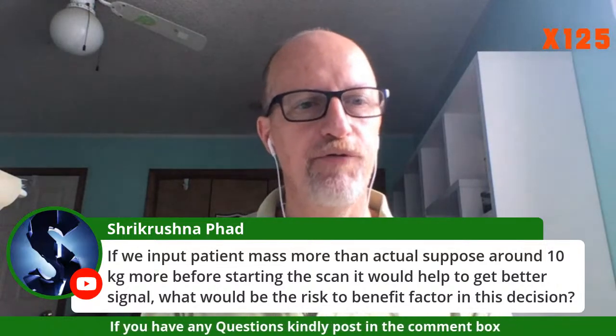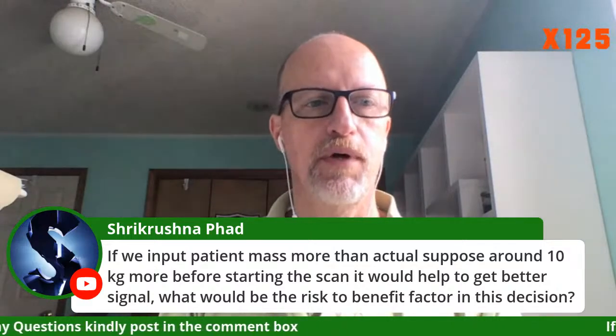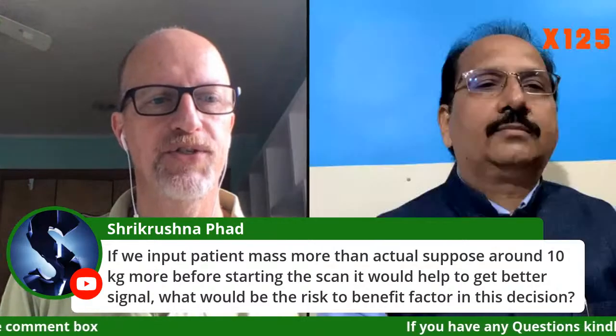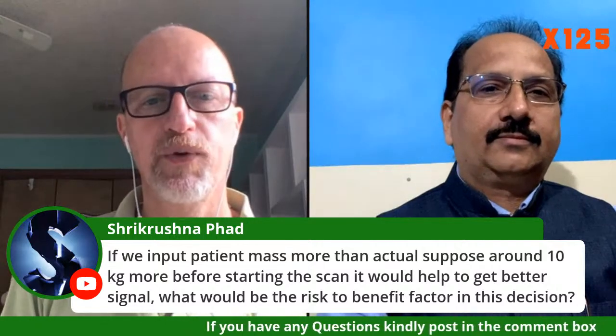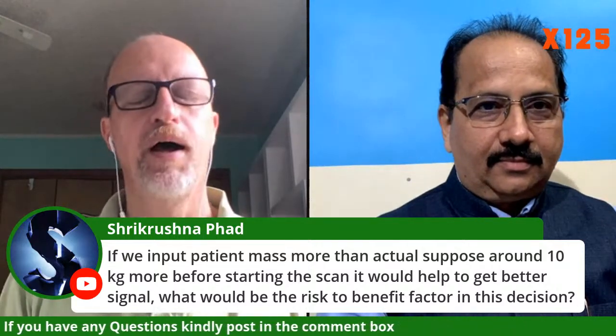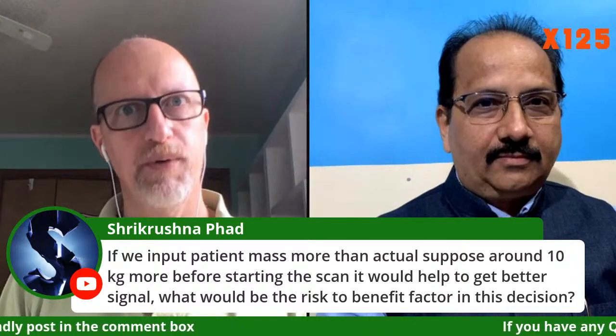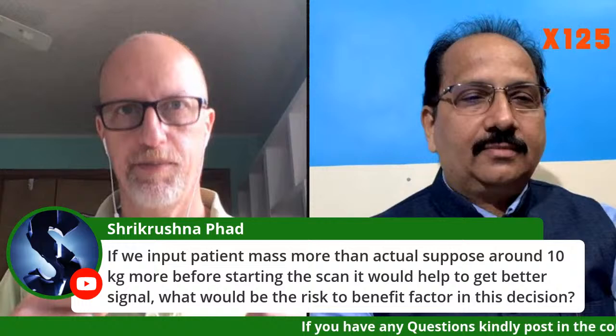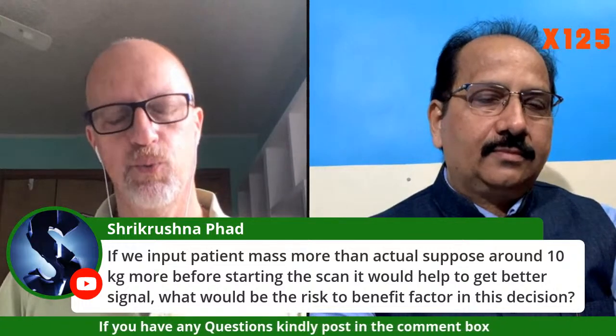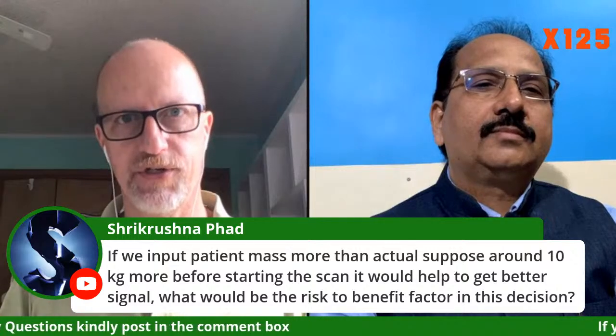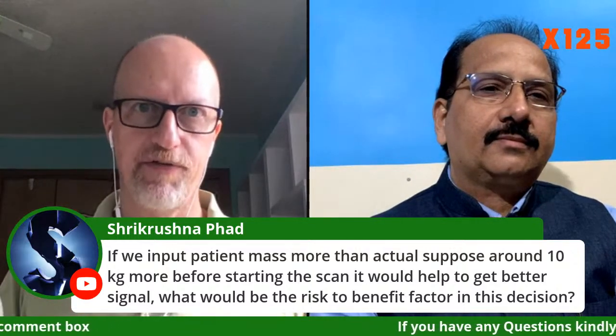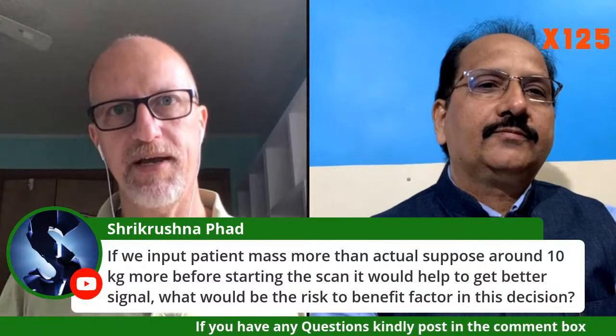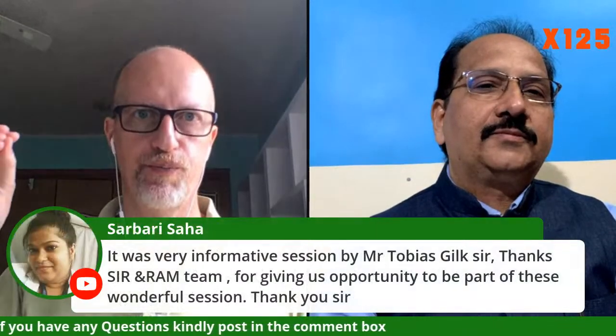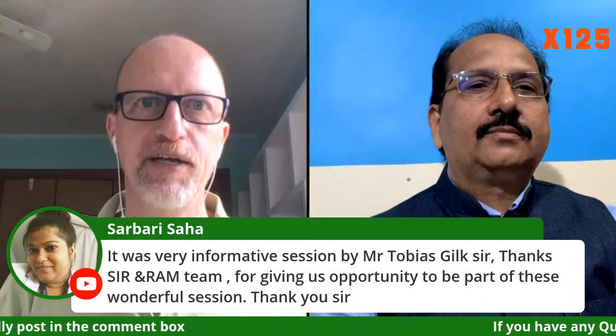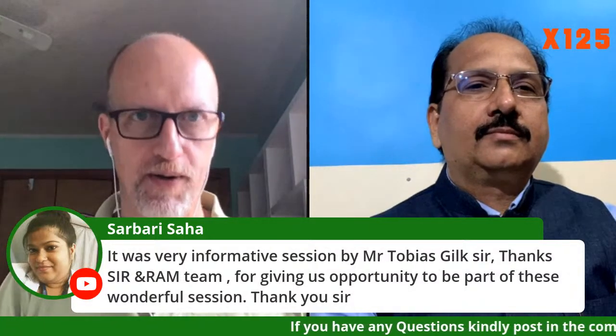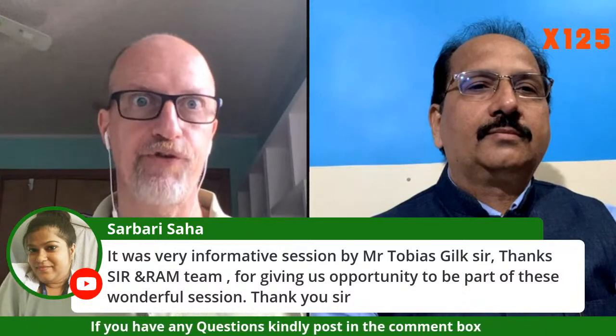Oh, here we have a question. If we input patient mass more than actual before starting the scan, will it help get better signal? What would be the risk-benefit factor in this decision? I would very strongly encourage you to use the appropriate, correct patient mass, because when you increase what you tell the system, when you increase the mass above the patient's actual mass, what you are telling the MR system to do is to produce more RF energy, to introduce greater RF power into that study, into that patient.